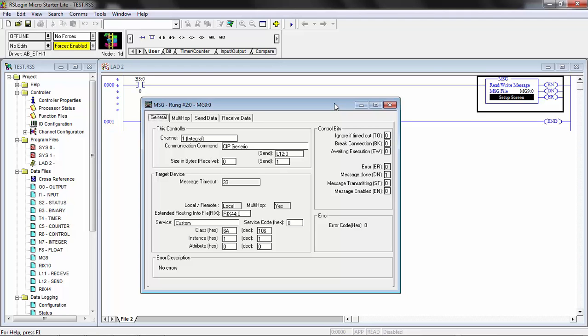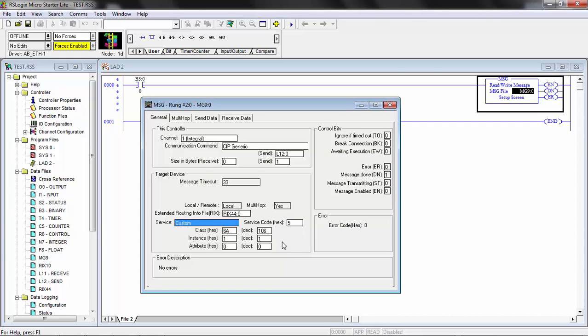So basically, it'll perform a reset to the controller if you want to start fresh. This message, most of it's been set up already ahead of time, this custom service. So it's custom service 05 hex is the code for the reset service. I'll put a 5 in, 5 hex in for the service code.